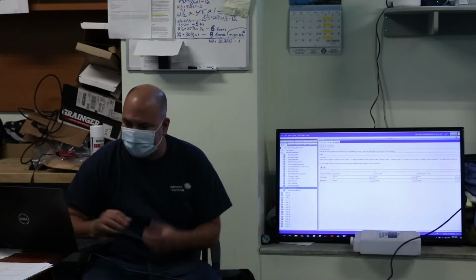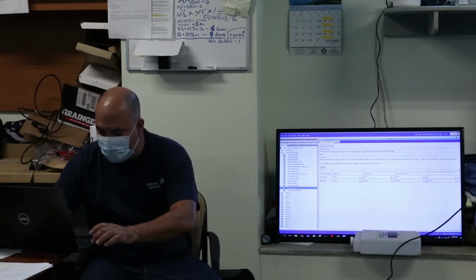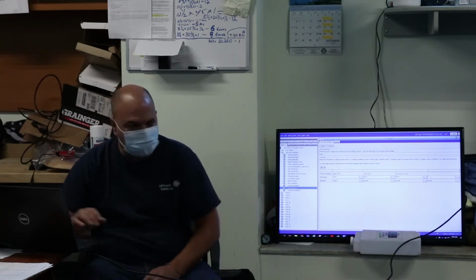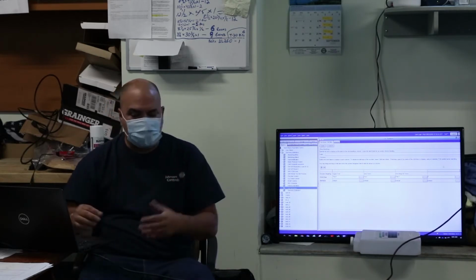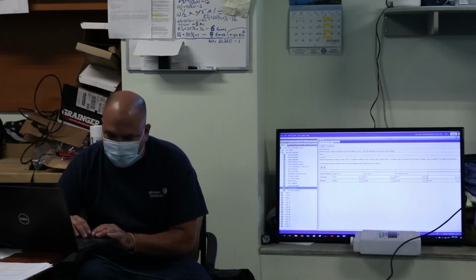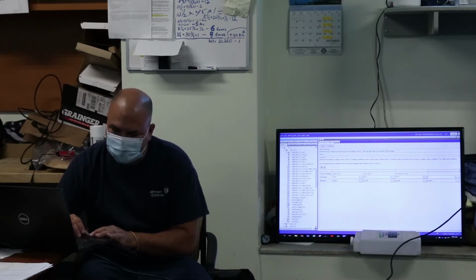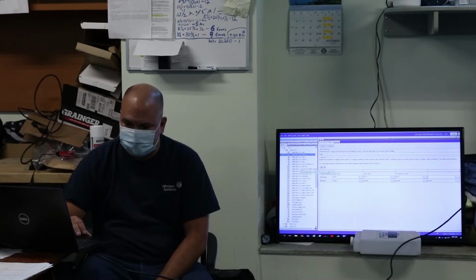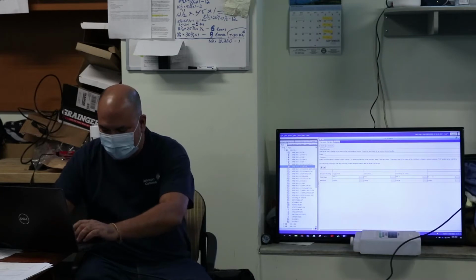We'll hit the edit button, and we'll hit the plus, and see how that adds us another row? So let's put the heating valve. Now we're going to use that asterisk again in front of the signal. And if you're not sure exactly what it's tagged, you could look at the VAV, where we could drop open the tree and look at what the points are tagged. We can see that the heating valve is tagged HTG-O. If we wanted to do zone set point, we could look at that. So let's do the heating valve.